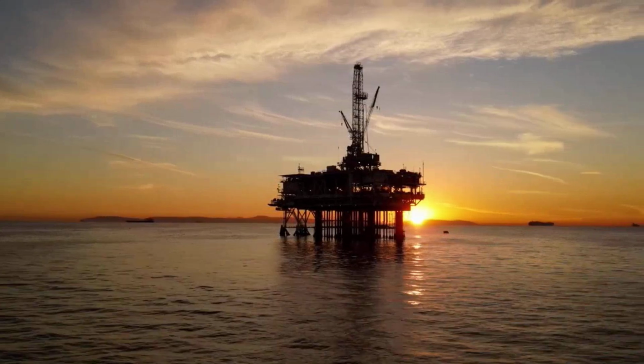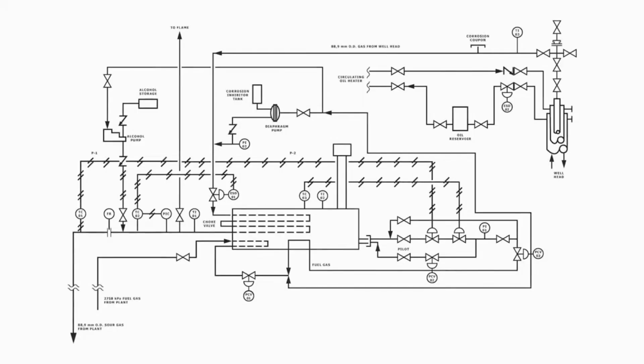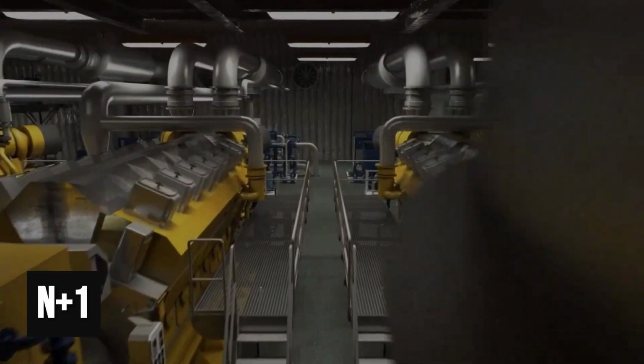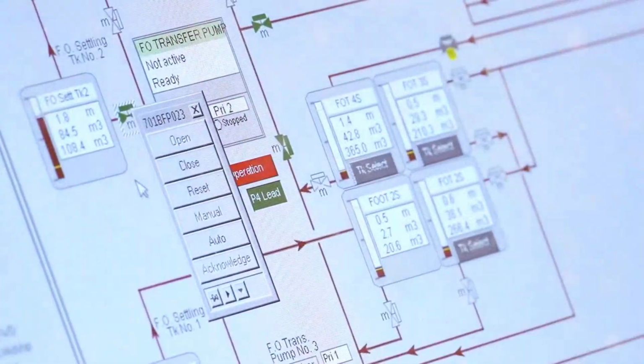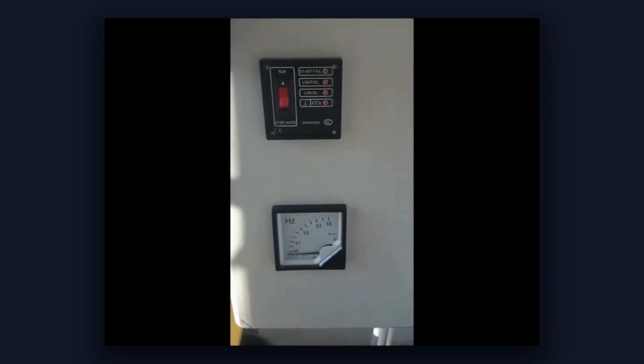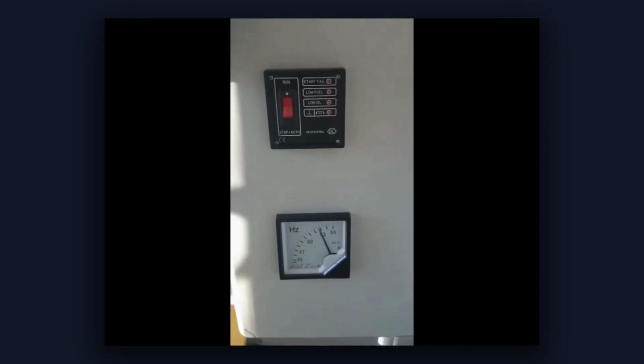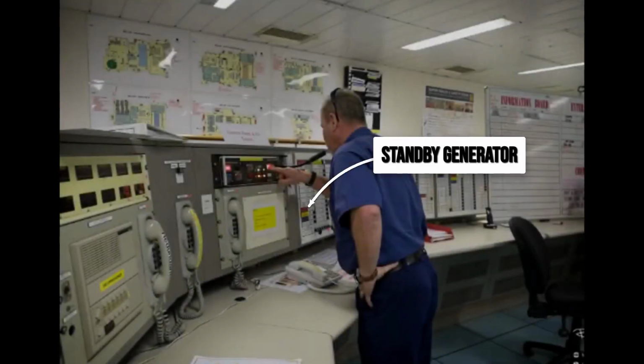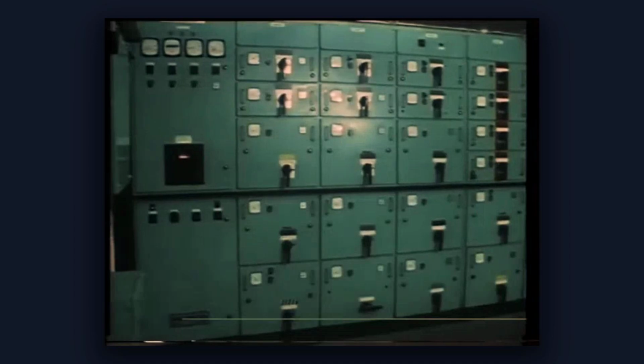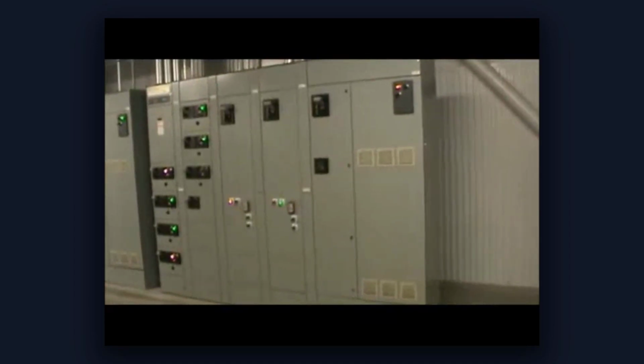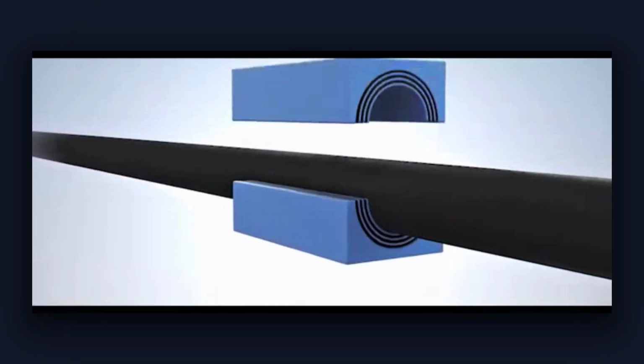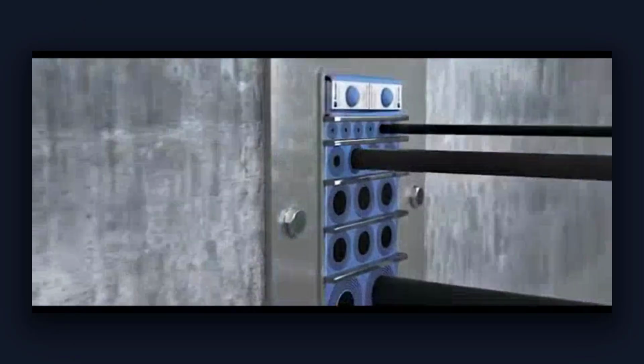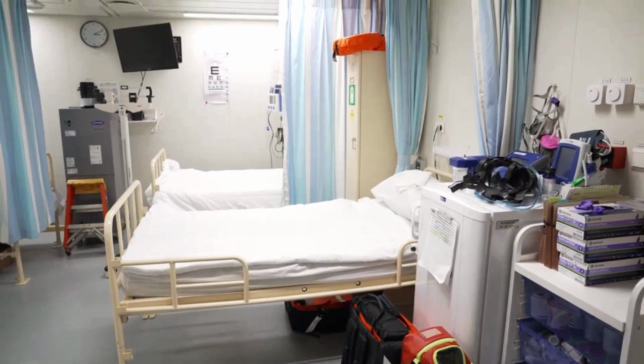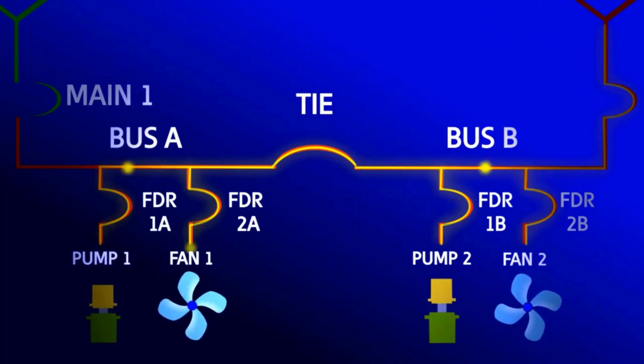Redundancy on an offshore platform is not an abstract idea. It is measured, calculated, and built into every critical system. For electrical power, the standard is N+1, which means one more generator than the maximum expected load. If the platform needs 3 generators to run at full capacity, a 4th stands by, ready to start automatically within seconds if one fails. Essential systems such as lights, communications, fire pumps, and water makers are wired to isolated emergency buses. These buses are physically separated from the main grid, shielded by fireproof bulkheads, and supplied by independent cabling. In a blackout, emergency power is guaranteed for life-critical loads, even if the main switchboard is lost.